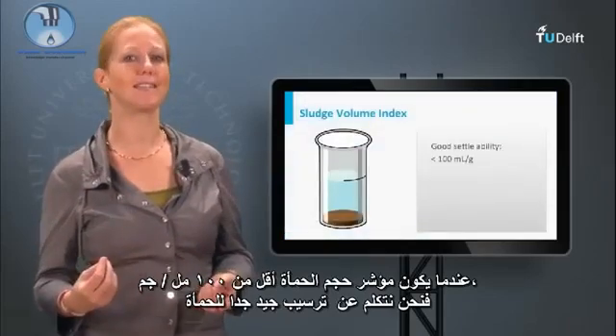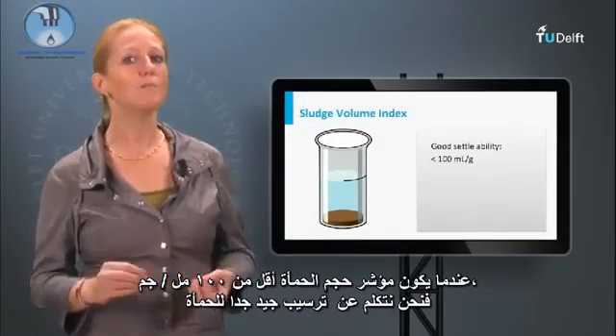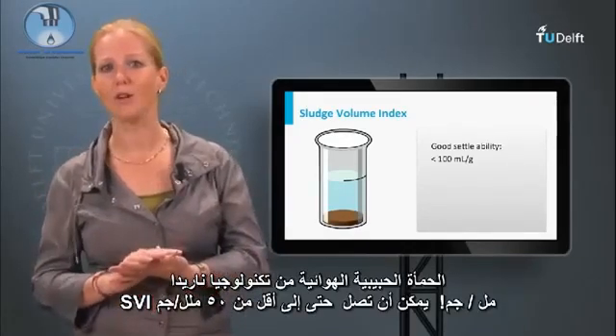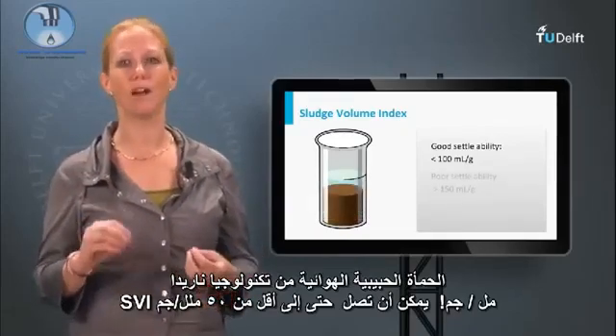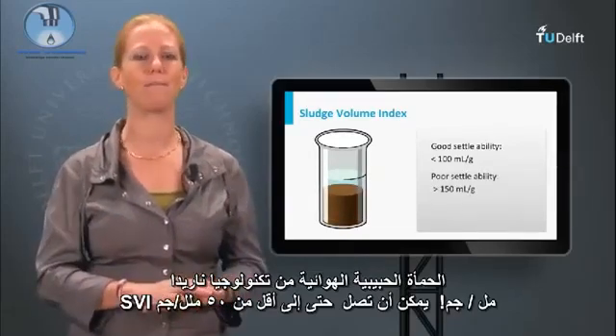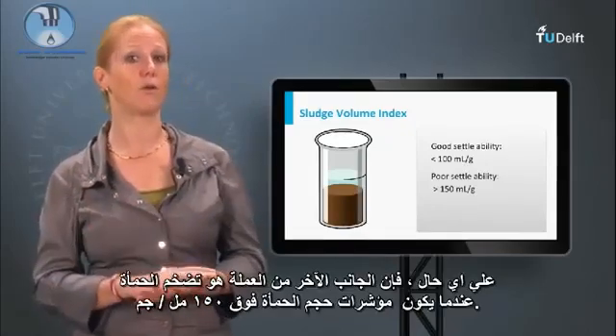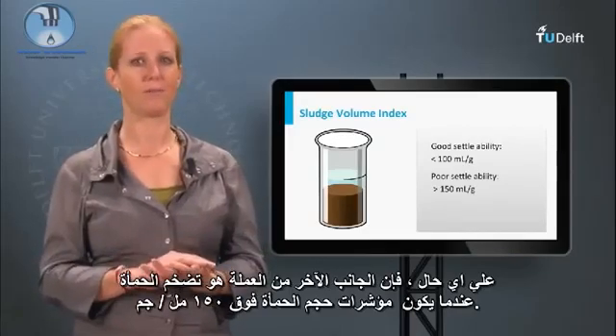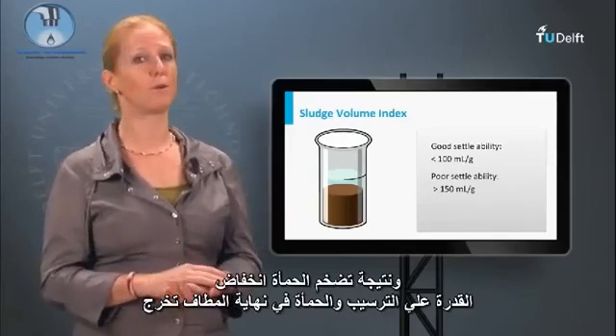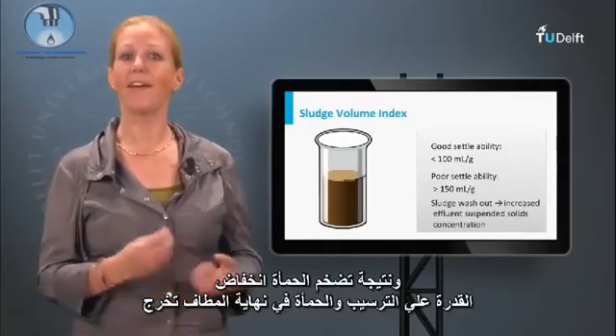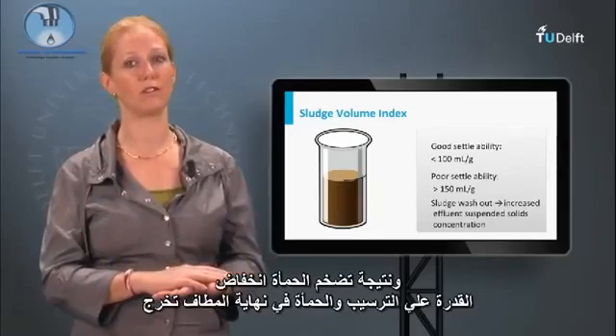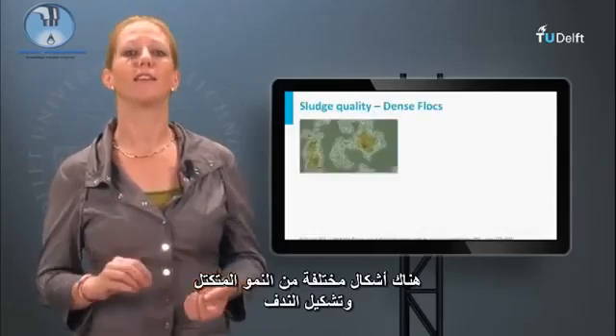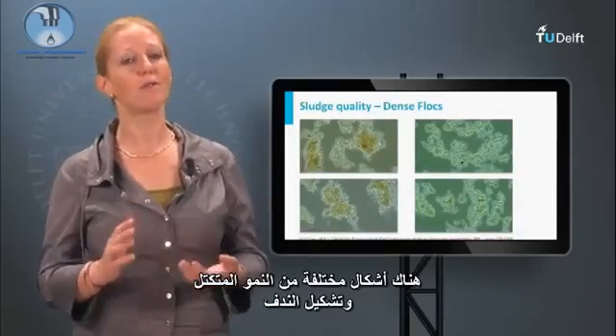When the sludge volume index is below 100 milliliters per gram, we speak about very well settling sludge. Aerobic granular sludge from the Nereda technology can even reach SVIs below 50 milliliters per gram. The other side of the coin is bulking sludge, when sludge volume indexes are above 150 milliliters per gram. The consequence is decreased settleability and eventually sludge washout — an increased effluent suspended solids concentration.